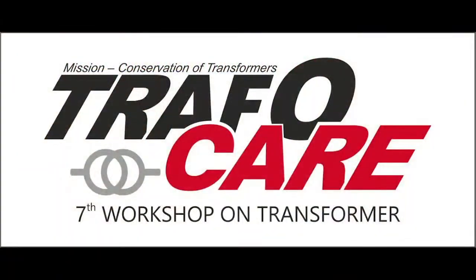Let me tell you, the tendency of that write-up is not to have the OLTC, but at the same time, such a sudden decision cannot be taken. Okay, so they left it open, as per the utility's choice to have OLTC or not. But let me tell you, NTPC, anybody here from NTPC? NTPC in their GT have removed OLTC. Okay, off-load tap changer is there. Even NHPC is telling.